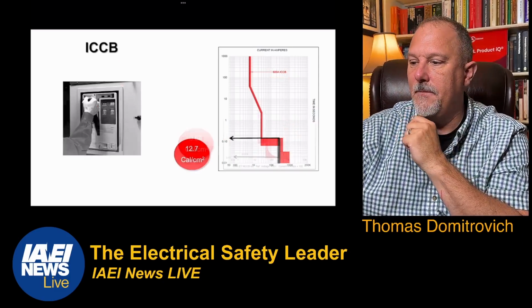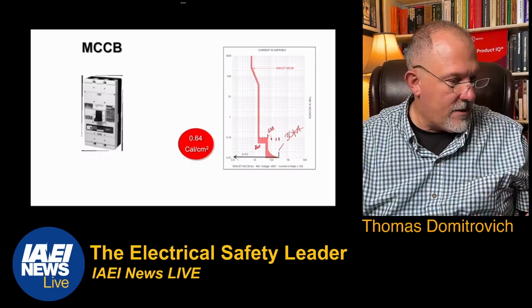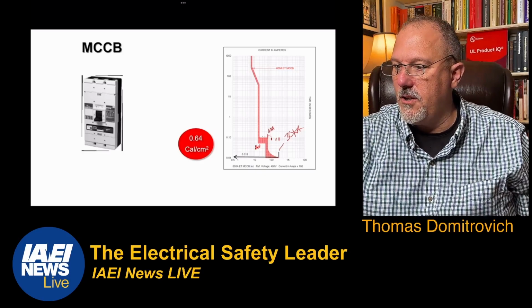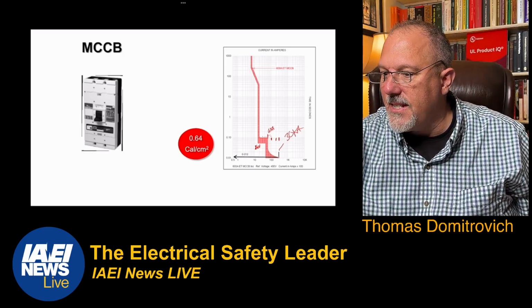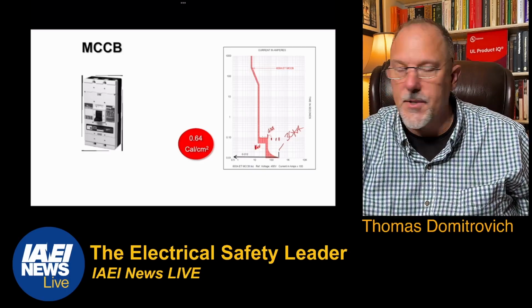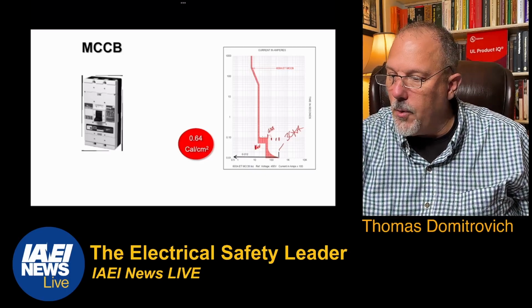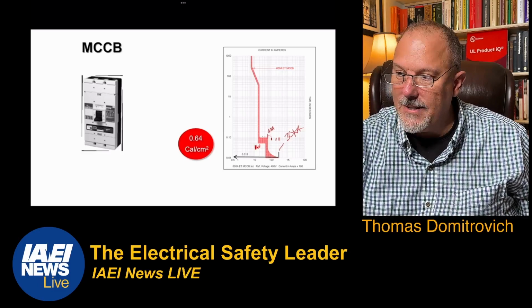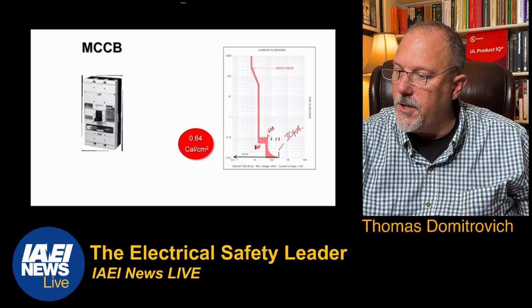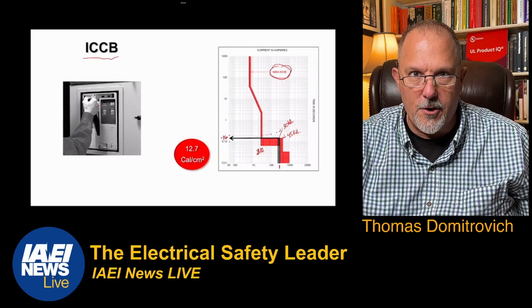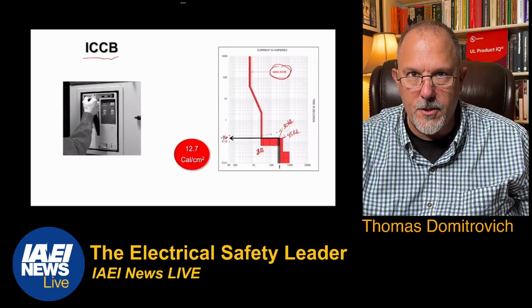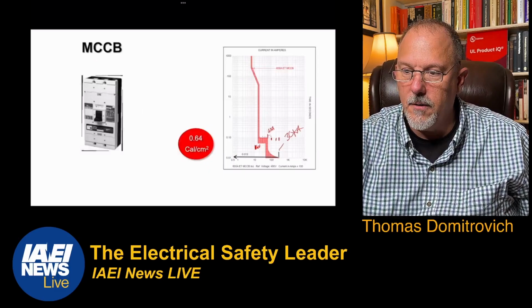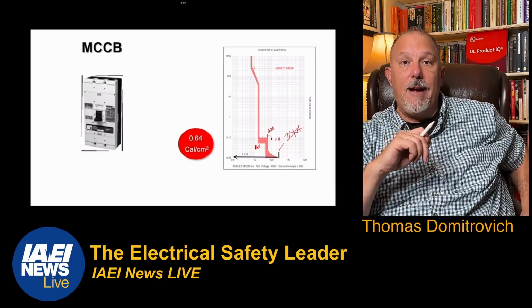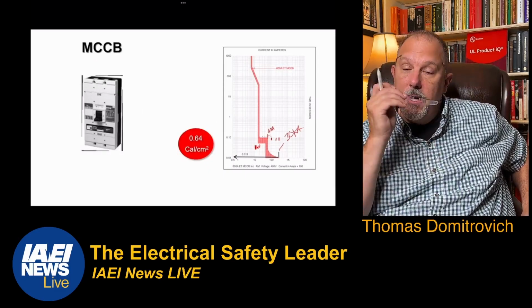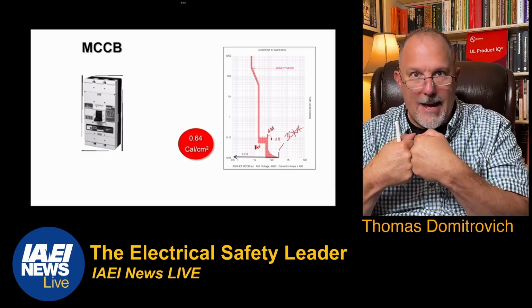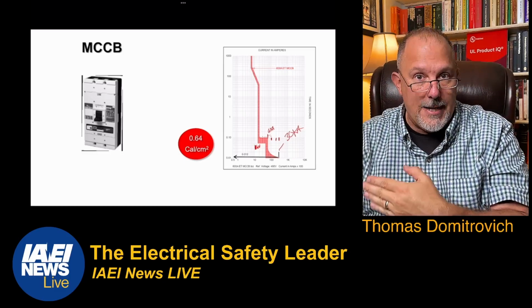Look at this delay. The short time delay on this molded case circuit breaker only goes from 1,600 to 6,000 amps, and that's at 0.1 seconds. If I would apply this same performance curve to this breaker, you would have an unintended rapid disassembly in the field. Why? Because these contacts can't take that much current for that much time.